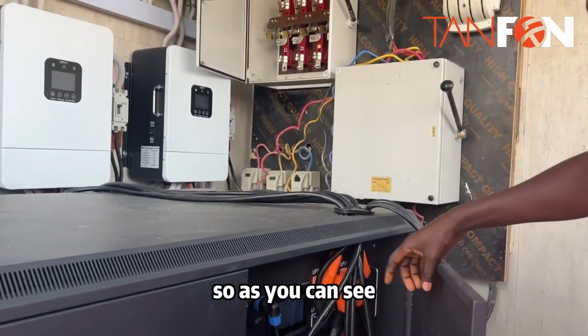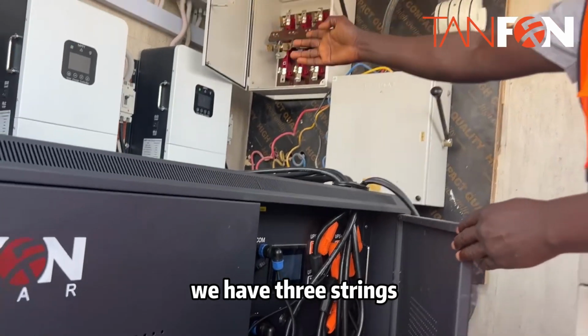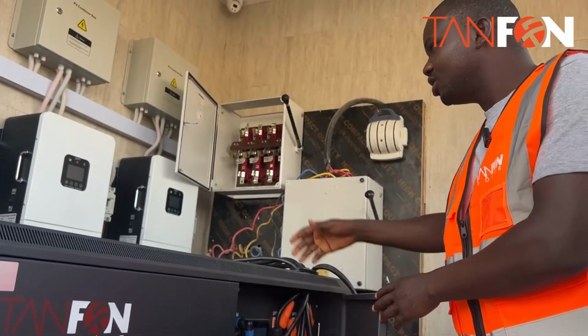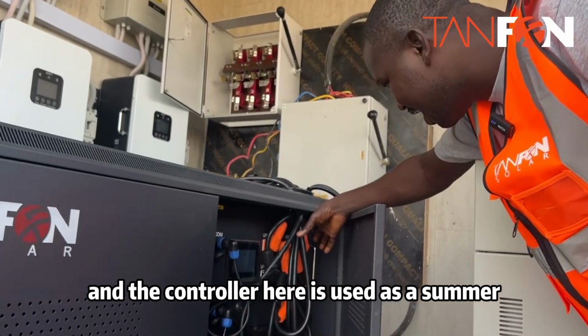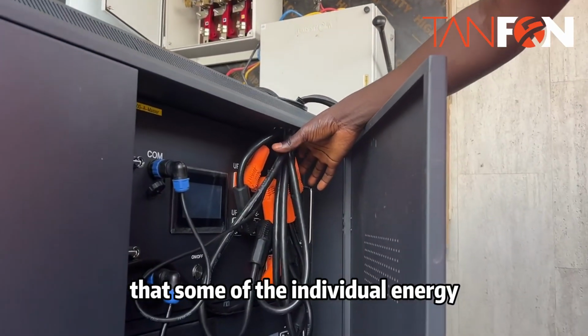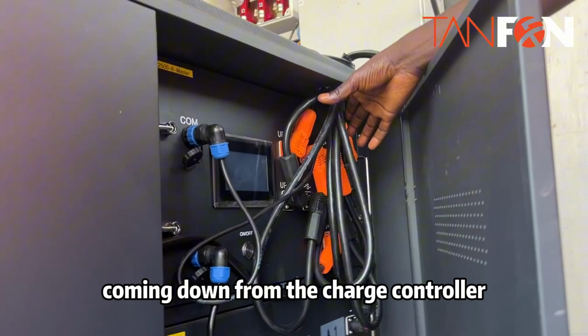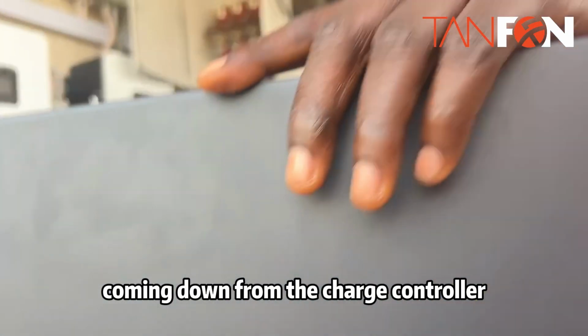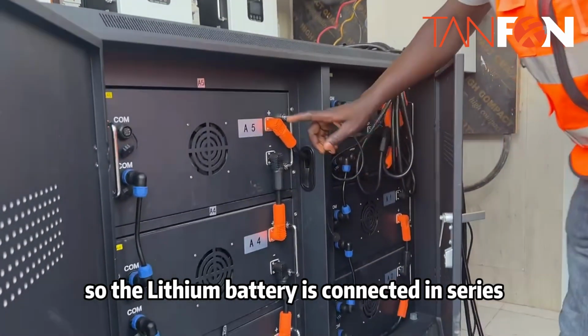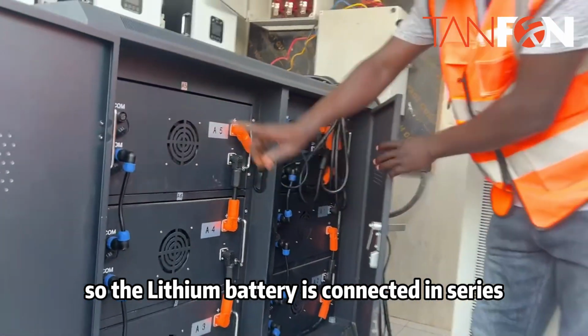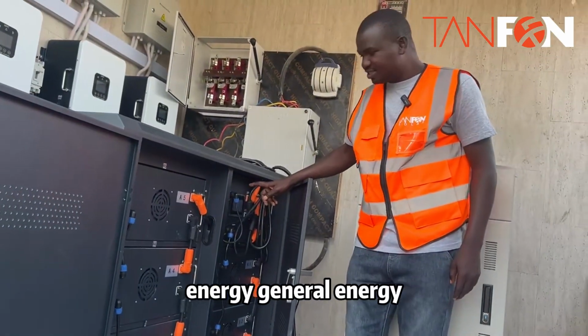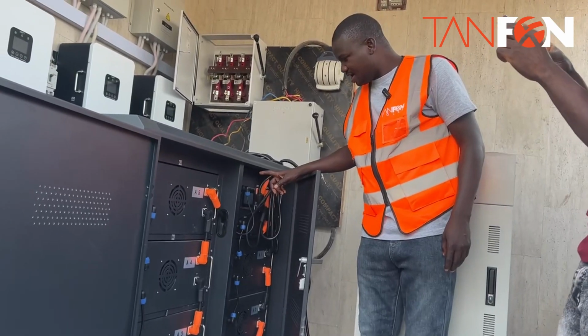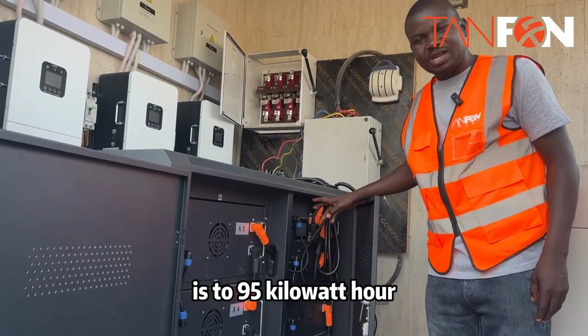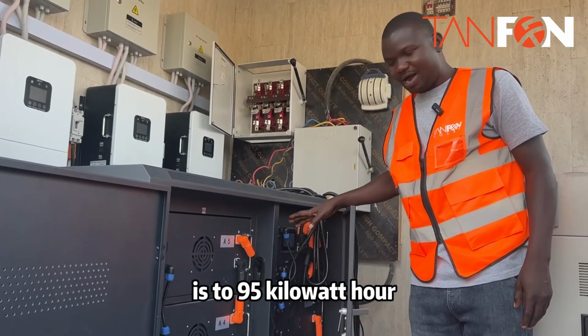As you can see, we have 3 strings and 3 combiner boxes, and the controller here acts as a summer that sums up the individual energy coming down from the charge controllers. The lithium battery is connected in series, and the total energy adds up to 95 kilowatt hours.